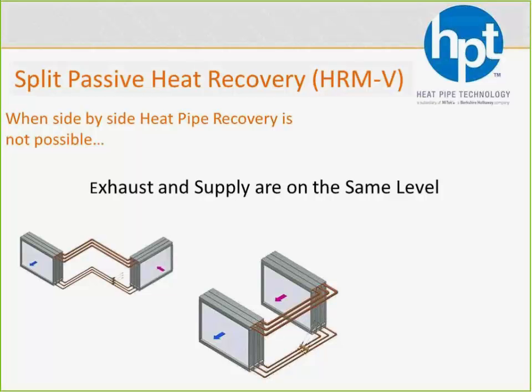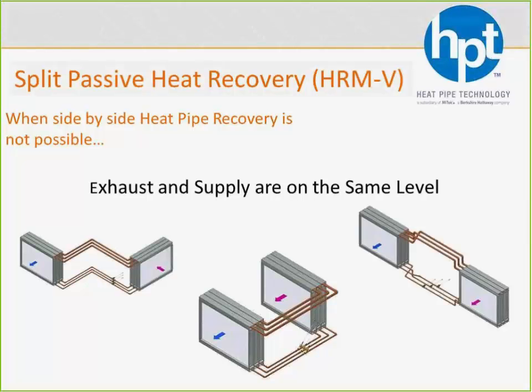You also notice there that there's some valves on the liquid line. Those are modulating valves. We can start modulating the refrigerant flow for temperature control. So if we're capturing too much heat, say we're in economizer mode, or even for frost control, you want to start limiting how much heat recovery you're getting. We can start modulating the flow to control that temperature. Another cool thing this allows us to do is take a parallel flow situation and make it counterflow. So if we had the side-by-side HRM and had to be parallel airflow, we're going to lose some performance.